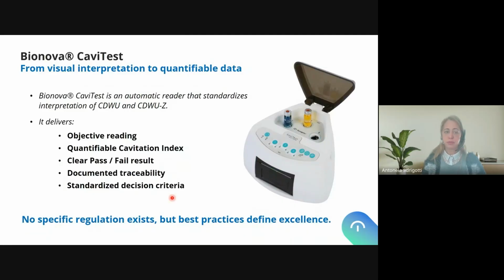Okay, so this auto reader will allow you to change the visual interpretation into quantifiable data, which is the aim of the machine and the objective of the webinar. So this machine delivers objective reading, quantifiable cavitation index, clear pass-fail results, documented traceability, and standardized decision criteria. No specific regulation exists, but best practices define excellence. So this is what we want when we offer our products, and this product is not the exception.